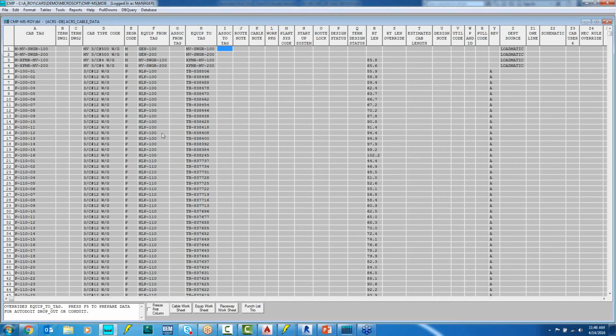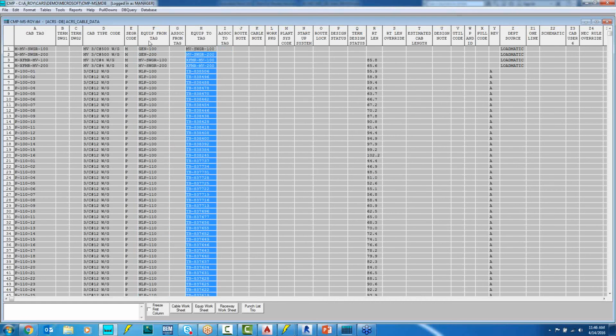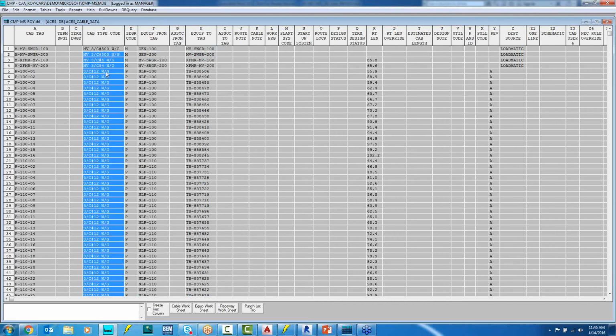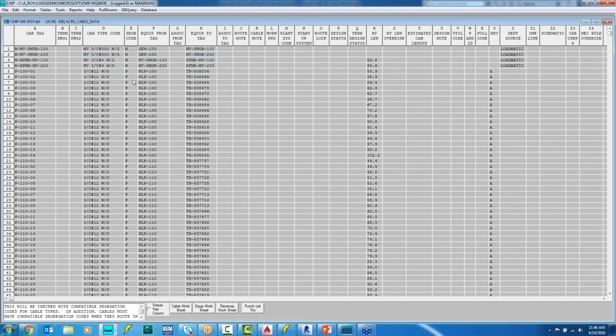This is just an interface, a front end to interface to our database. Because as you know, databases are very delicate and very sensitive, and there is no undo. Well, this allows us to query the database, pull in the information that we need, and then manipulate it and then save it back to our database. So in order to route cable, we will need a unique cable tag, a from and a to on our equipment, and a cable type or cable specification, and we'll also need to know the voltage level. The program will not put a medium voltage cable, for example, in a low voltage or a safety tray. So we have to identify the voltage level of each cable and associate that to the service level of the raceways that we're going to be routing them in.